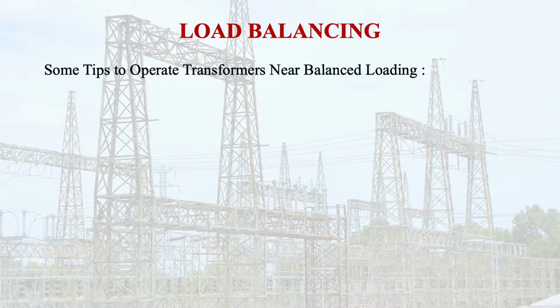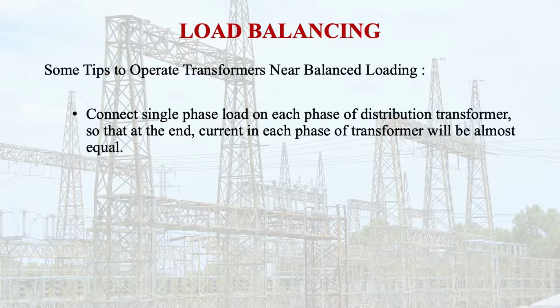So we offer some tips for this. What are these tips? Some tips to operate the transformer near balanced loading. For this, connect the single phase loads on each phase of the distribution transformer so that, at the end, the current in each phase of the transformer will be almost equal.